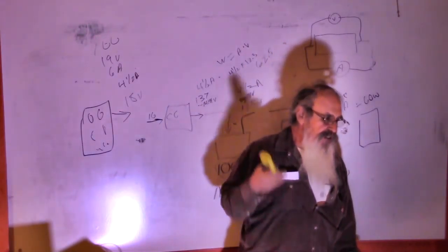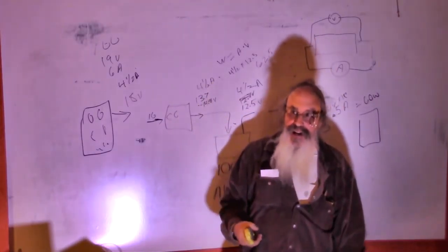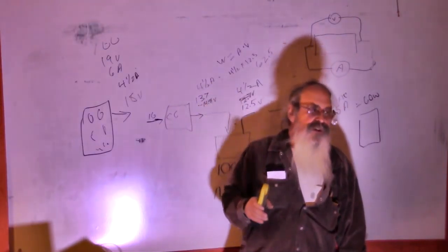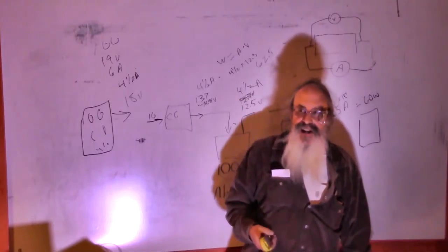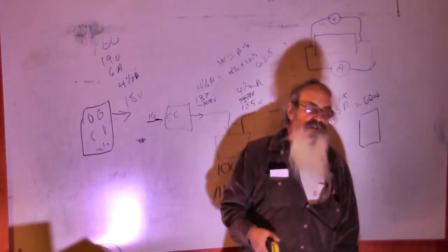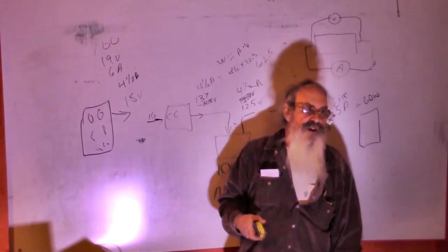If the motor says it's supposed to be drawing 7 amps and you're drawing 9, you make the pulley smaller again, because pulling 9 amps through a motor rated for 7 will make the motor get hot and burn itself out. So anyway, somewhere in here, there it is.